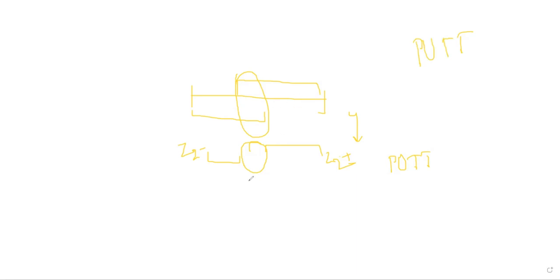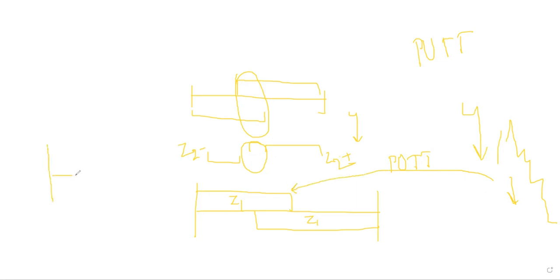Now you are trying to say something about this overlapping, because I still could not understand which type of fault this is. This is the zone 1 for this relay, and this is the zone 1 for this relay, right? Correct. So this is the overlapping. Maybe due to the arc fault resistance, a severe fault occurred. This is a ground fault, right? Maybe the arc formation of this severe fault or the ground resistance makes this impedance show an effect. So in some cases, this relay is seeing the fault in zone 2, and this relay is also seeing the fault in zone 2 only, meaning it is appearing in the middle.